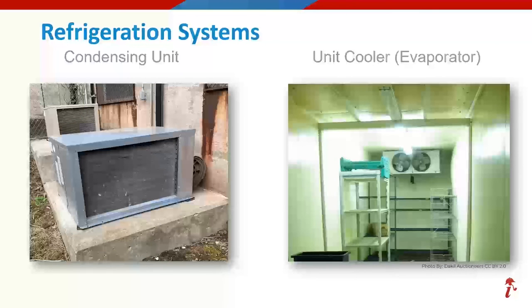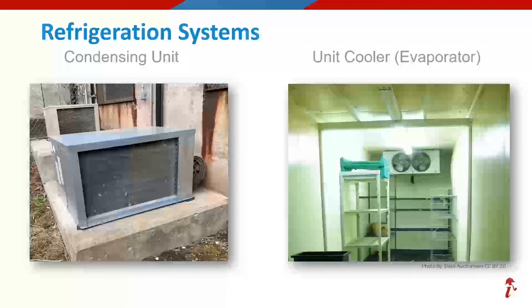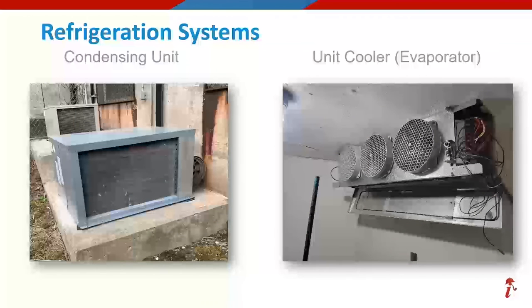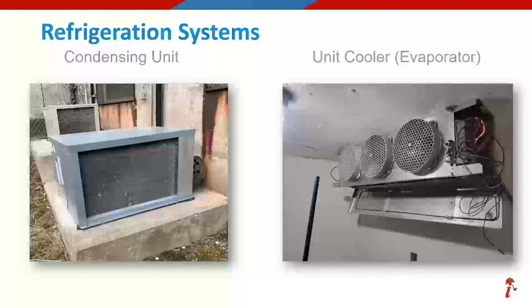Now looking on the right side of the screen, we see the inside of a walk-in unit. And we see the example of a two-fan unit and notice how it is installed where the wall meets the ceiling, which is the most common. Here we see a larger, newer three-fan unit opened up. We can see the wiring and electronic controls.